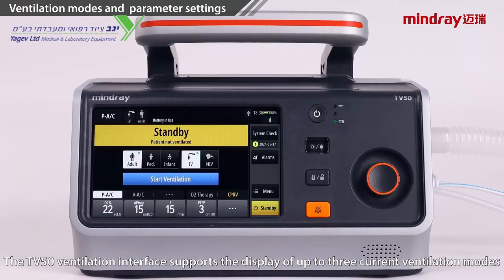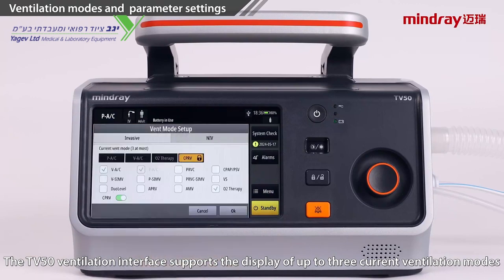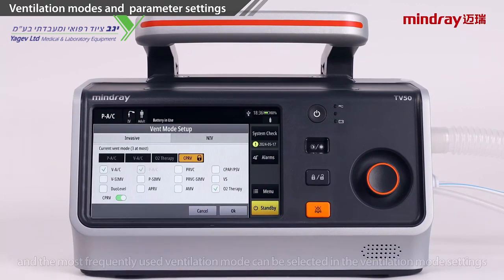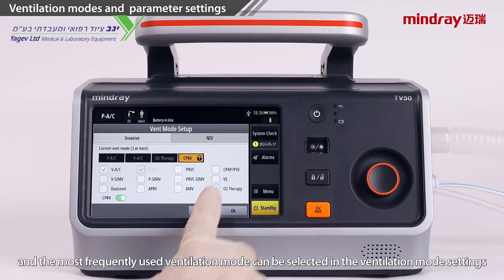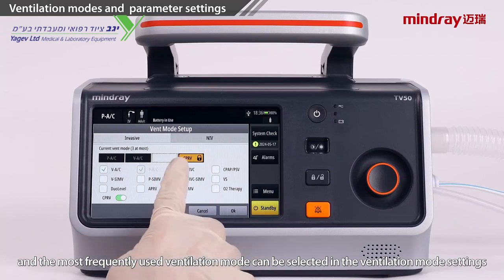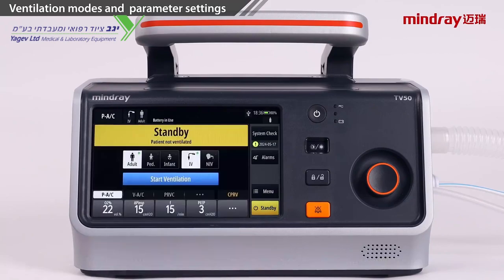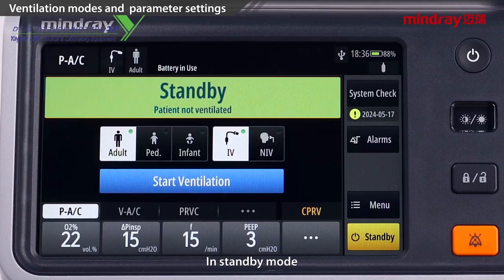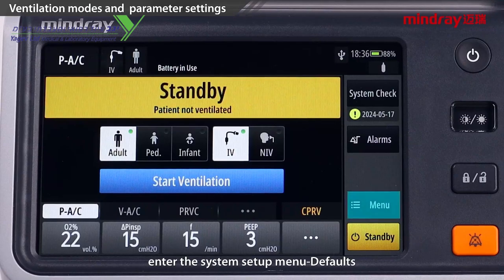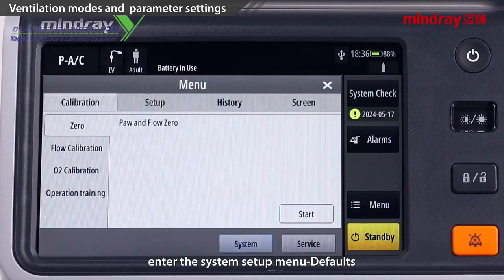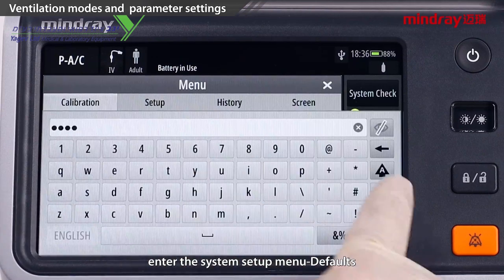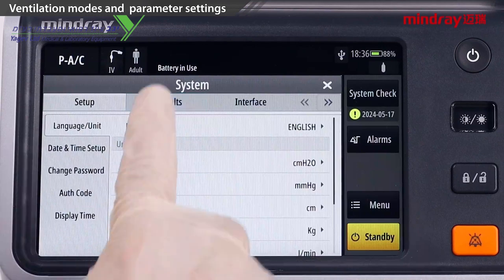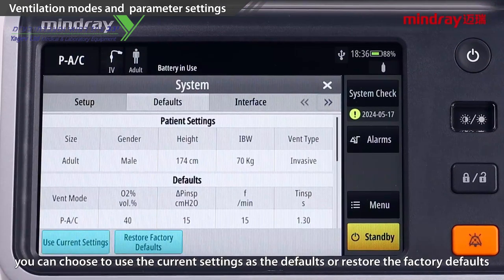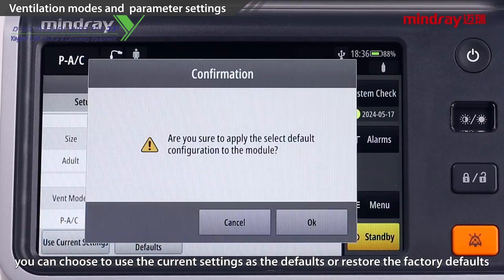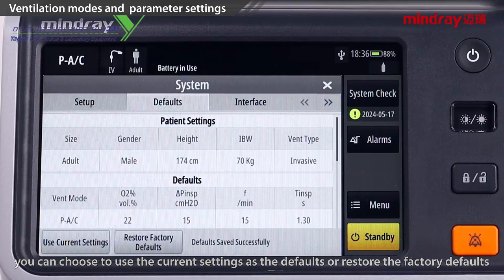The TV50 ventilation interface supports the display of up to 3 current ventilation modes, and the most frequently used ventilation mode can be selected in the ventilation mode settings. In standby mode, enter the System Setup menu, Defaults, and you can choose to use the current settings as the defaults or restore the factory defaults.